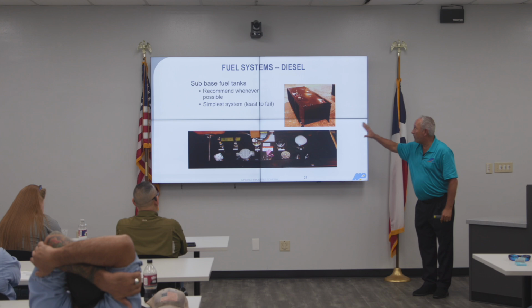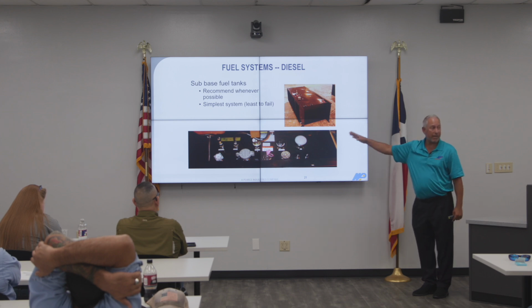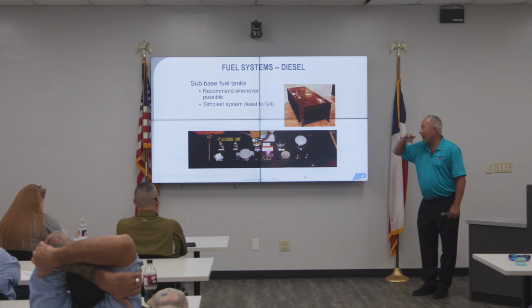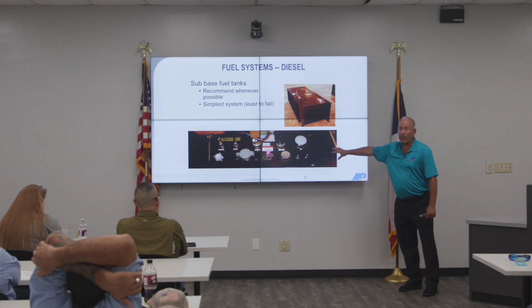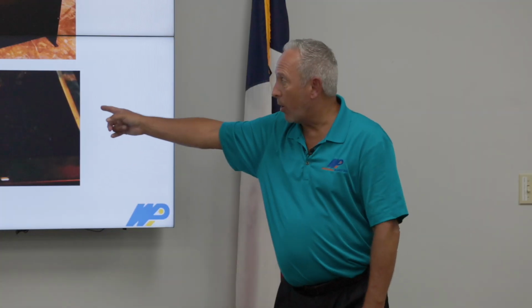But most of the OEMs, they'll make it themselves and bring it here. They refer to these as a UL 142 tank, a double wall tank. That means if the inner wall breaches, the outer wall will contain the fuel, so you don't have a fuel spill. There are monitors in there to tell you if you got fuel in your outer wall, so you know there's an issue.